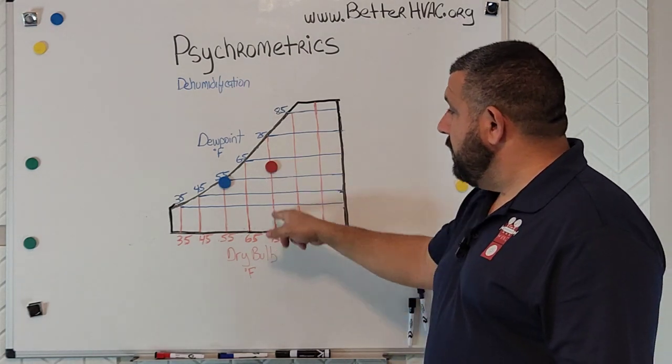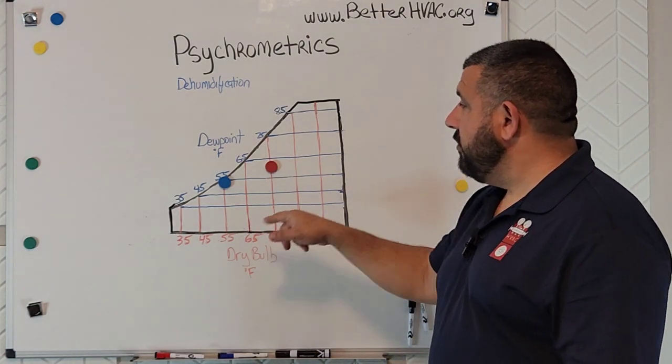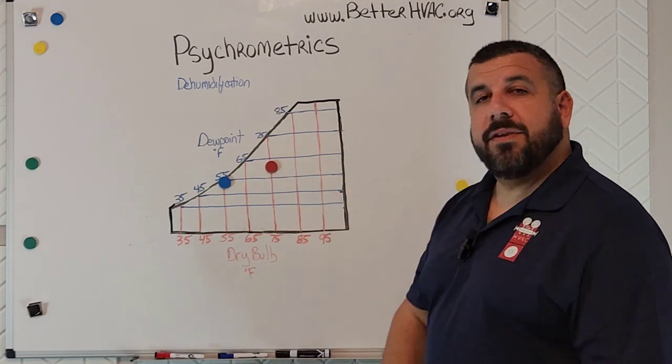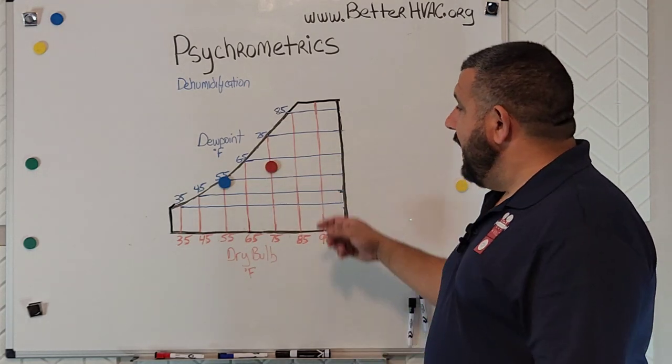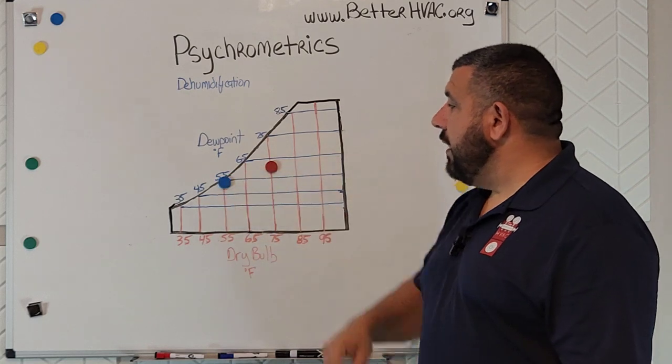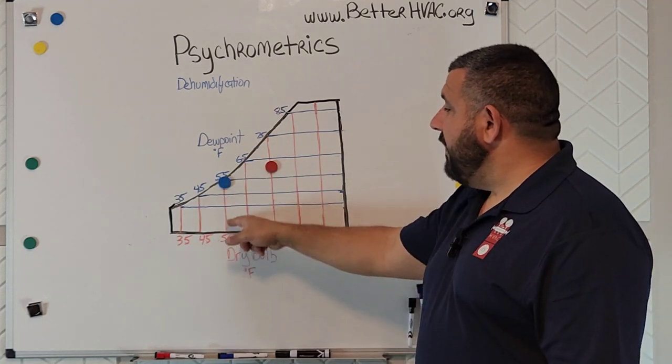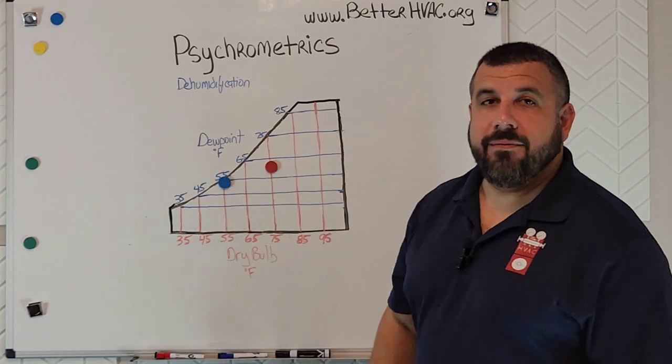So say, for example here, this is our typical return air temperature: 75 degree dry bulb, somewhere around a 60 degree dew point. And the air coming out, our supply air temperature, is around 55 degree dry bulb and 55 degree dew point.